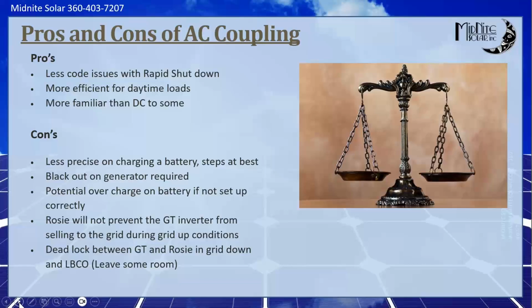The Rosie also will not prevent the grid tie inverter from selling to the grid during grid up conditions. So if you've got a customer who says, I want to install a system, I do not want a net meter, I want to do self-consumption, then AC coupling may not be the way to go, because when the Rosie connects to that grid and the relay closes, it cannot prevent the backflow of power to the grid. Virtually no battery-based inverter can do that. If any battery-based inverter closes its relay, it's really out of control what's going back out to the grid from that grid tie inverter. So that's just something to be aware of. If the customer does not want that net metering agreement, probably steer clear of AC coupled.